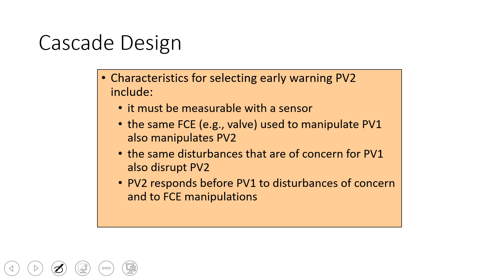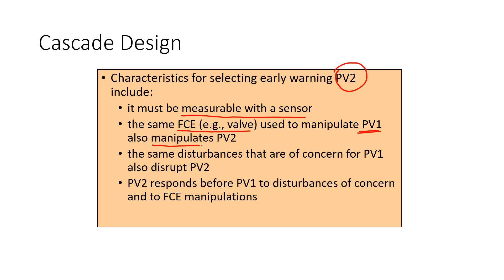Cascade design characteristics for selecting this early warning: in this case it might be flow, and it has to be measurable with a sensor. So we're adding an additional sensor to our feedback controller and setting up an inner feedback loop. We also have to use the same final control element — for example, a valve that's used to manipulate the outer loop PV also manipulates the inner loop PV. The same disturbances that are of concern for PV1 also disrupt PV2. And we need PV2 to respond to set point changes of the inner loop much faster than the outer loop.